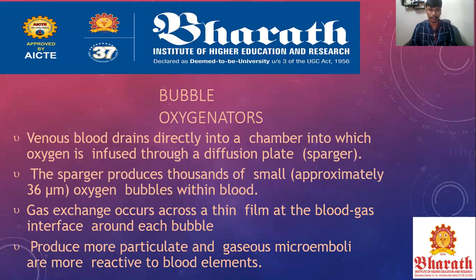But in the bubble oxygenator, the O2 or gas molecules are added into the blood flow stream. Venous blood drains directly into a chamber into which oxygen is infused through the diffusion plate. The diffusion plate is technically known as a sparger. Using the sparger, oxygen is diffused into the bloodstream. The sparger produces thousands of small oxygen bubbles within the blood, and gas exchange occurs across a thin film at the blood-gas interface around each bubble.